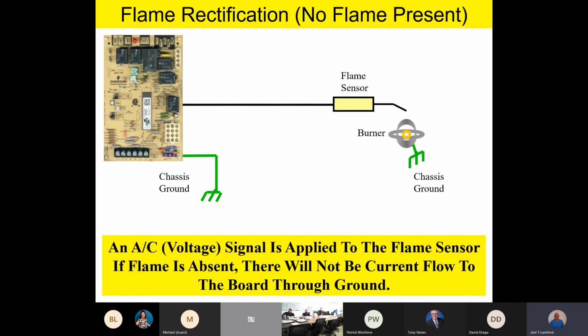Now this is interesting because the flame sensor is actually powered up anytime the furnace is powered up. So if you've got power to the furnace, you're going to have line voltage on the flame sensor. A lot of technicians don't realize that. However, that circuitry is an extremely high resistance circuit. So if you were to touch the flame sensor, or if it was shorted to ground, it's not going to burn anything up. It won't even shock you, because we're talking about hundreds of millions of ohms of resistance. So even though there's voltage there, there's no current. We're talking into the microcurrent ranges here.